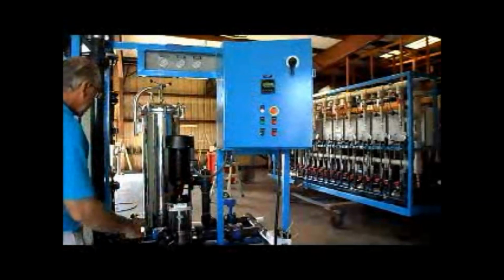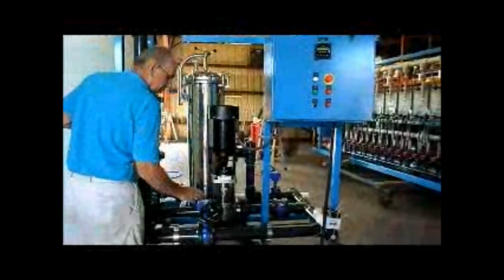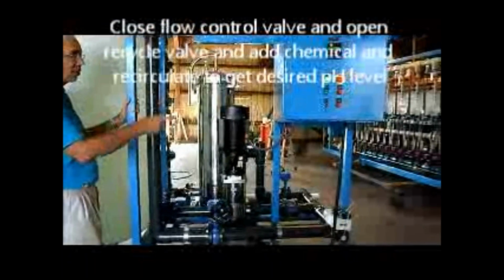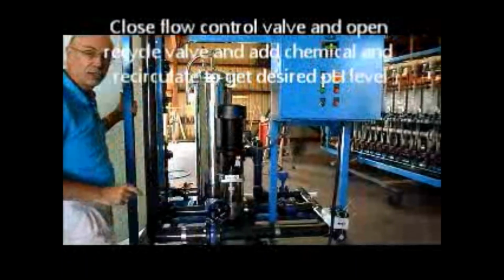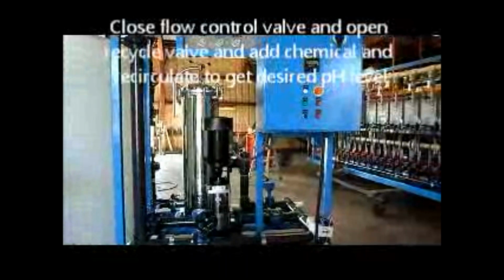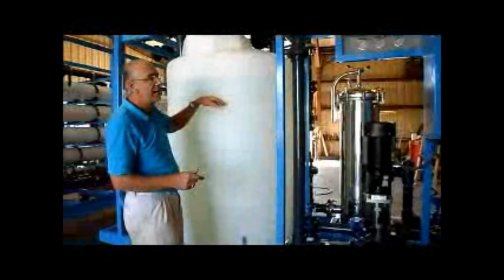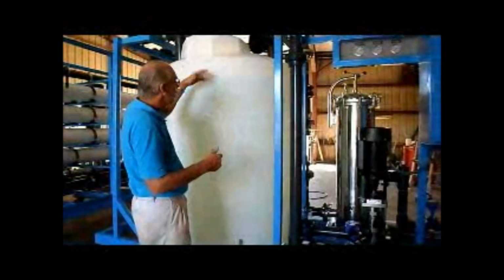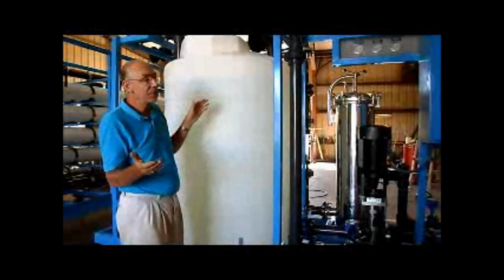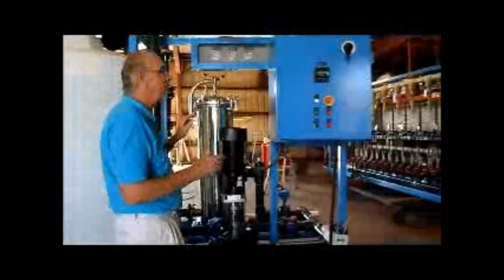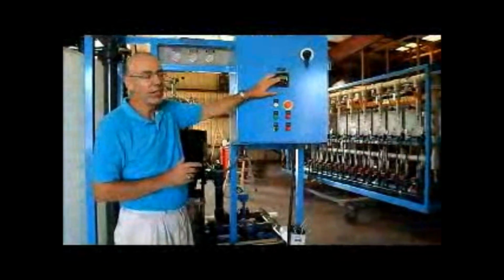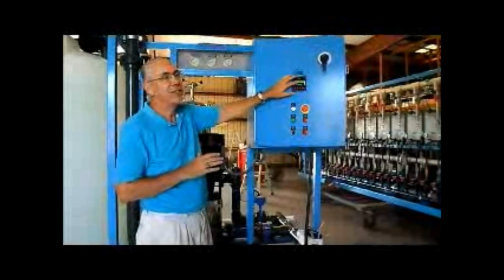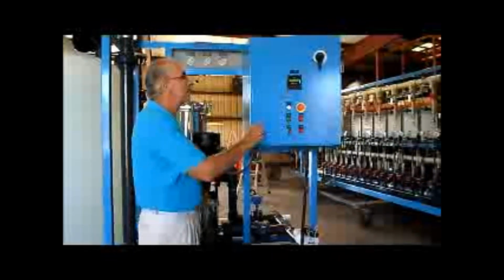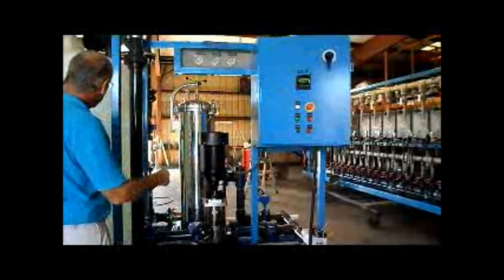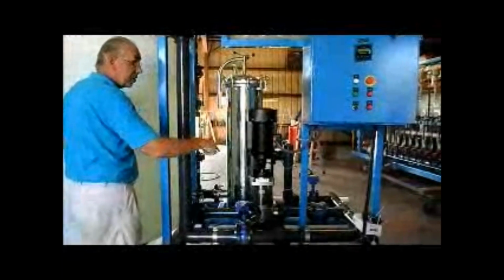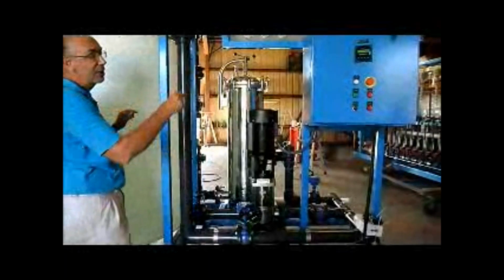What you do is, again, as we mentioned earlier, close that valve, open this valve, circulate your solution here until you see the pH in the range that you want. If it's too low, add some more acid, get the pH down. If it's too high, you're doing a high pH solution, not high enough, add some more caustic. If you get overshoot and it's too low, it's not such a problem. If let's say 2 to 3 is your target, so it's 1 to 2, that's not so important. If it's 11 to 12, it's not so important, if you're trying to get approximate ranges. But adjust your chemical concentration by recirculating back in the tank until you get the pH reading that you want.